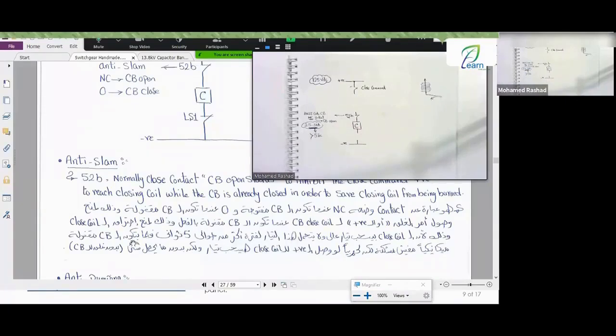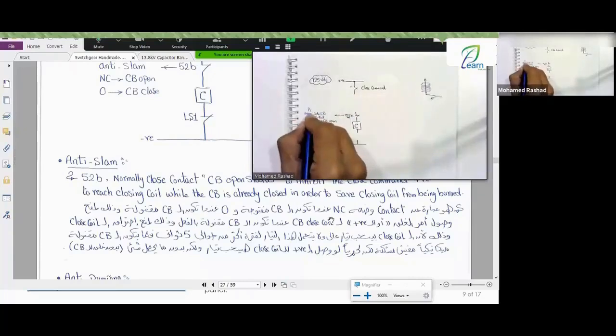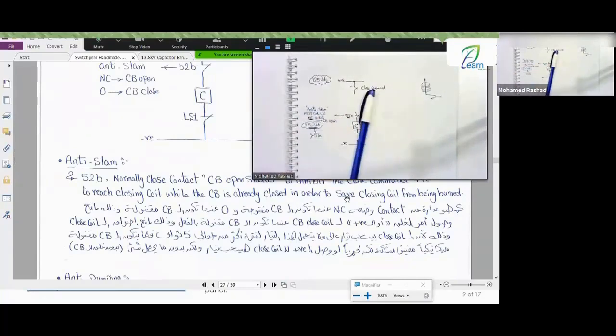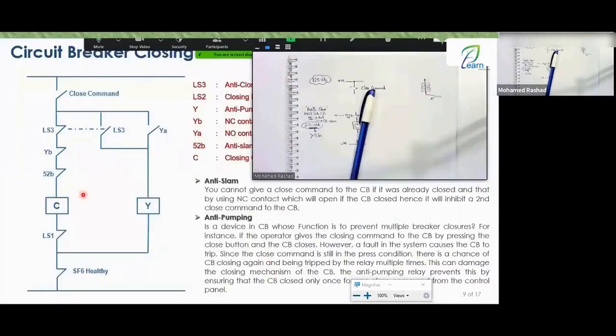So when the circuit breaker is mechanically closed, there is no problem. But if you accidentally connect DC to the closing coil, it will draw current without changing its position, and as a result, it will burn out. Is that clear, engineers? This concept is called what? We call this contact function anti-slam. All right, this is the part famously known as the anti-slam story. So the 52B is the anti-what? Anti-slam. Engineers, focus with me on these concepts, because for those who have booked the test for this course, I know that questions like this might come up.